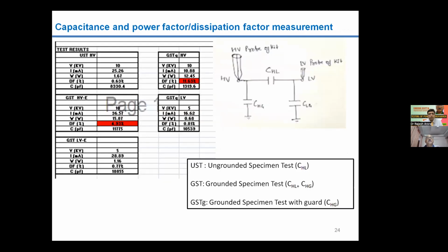And as I discussed, these are the results. The 5 measurements we are doing in BSES are the ungrounded specimen test, the grounded specimen test, and the grounded specimen test with guard. We will discuss each test in detail later, but tan delta measurement basically indicates the health of the insulation, or any change inside the geometry of the transformer winding, or that something wrong has taken place inside the transformer.